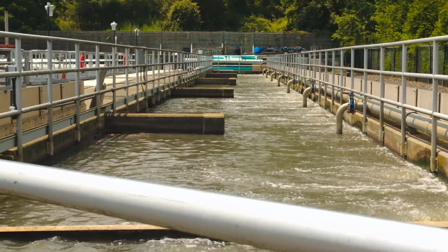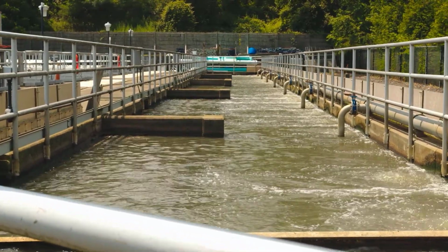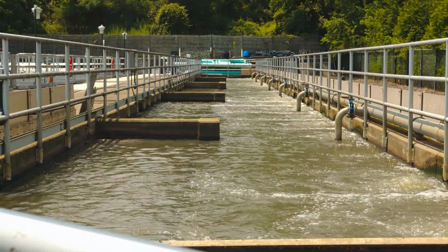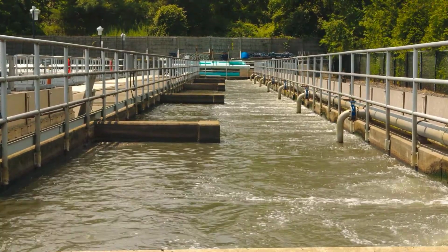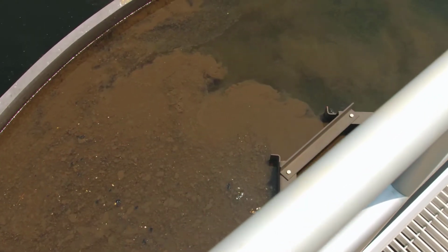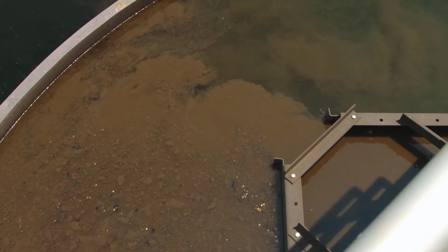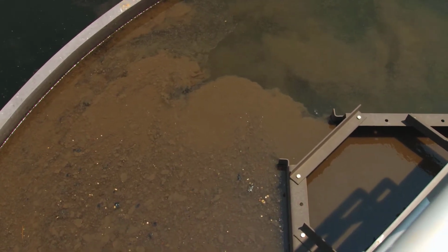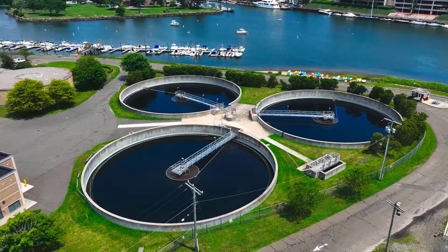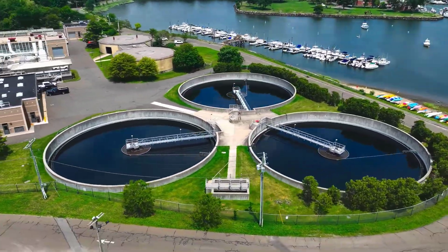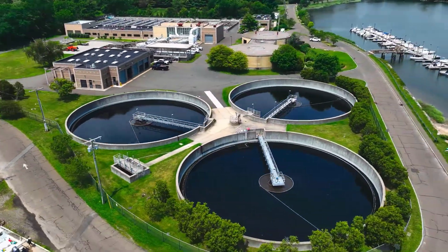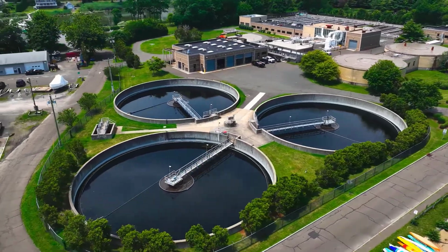The secondary treatment of wastewater involves processes such as aeration that enable microorganisms to biologically remove organic matter and contaminants. The microorganisms consume biodegradable soluble contaminants such as sugars, fats, detergent, and food waste using aerobic and anaerobic processes. Secondary clarifiers separate biological floc from the treated liquid waste stream and are often used in conjunction with suspended growth biological wastewater treatment plant systems.